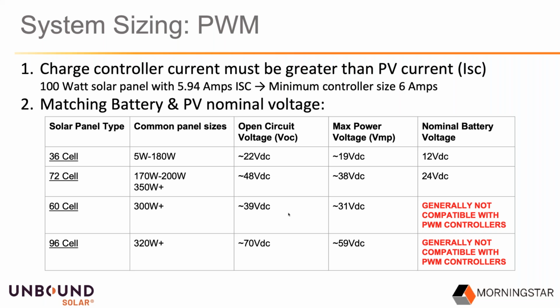Yeah, I'm just comparing the 72 cell module. You can see the open circuit voltage about 48, max power voltage about 38, as opposed to the 60 cell, which has open circuit 39 versus 31. So all the numbers here look to be right, that the 72 cell has higher voltages than the 60 cell. Yeah, and that's a good point.